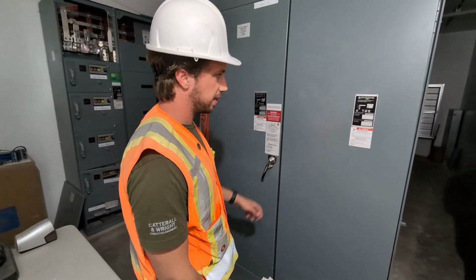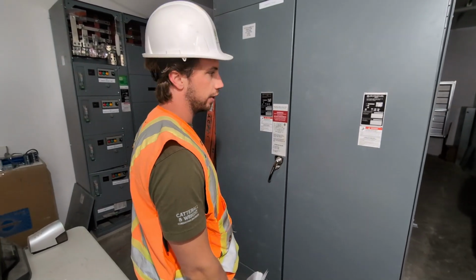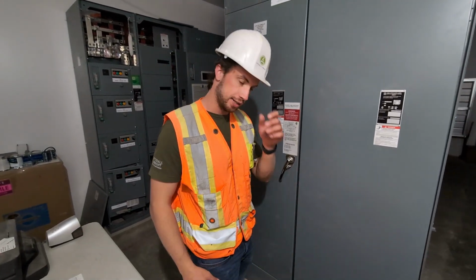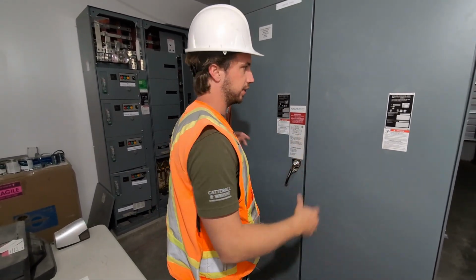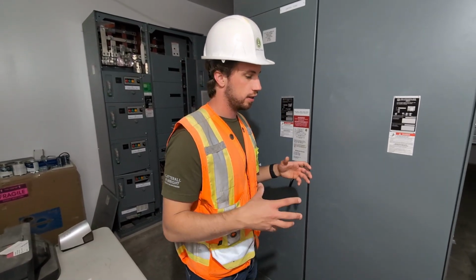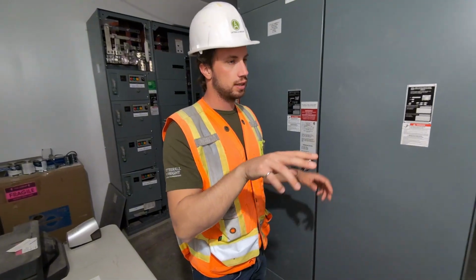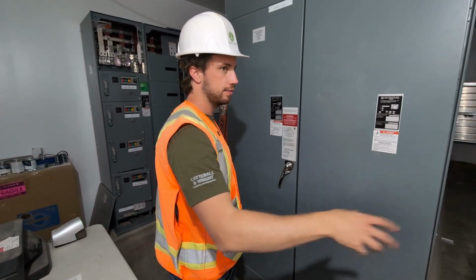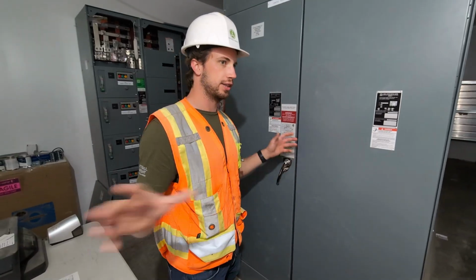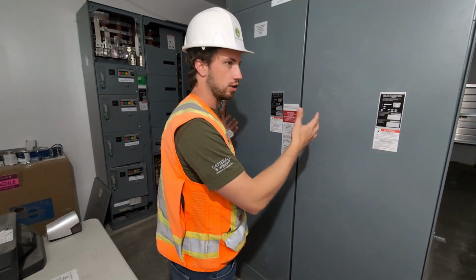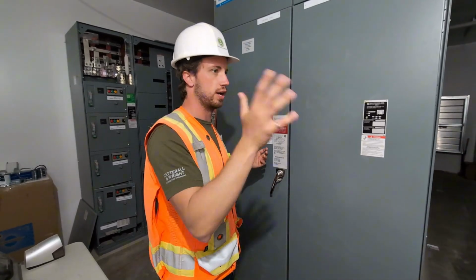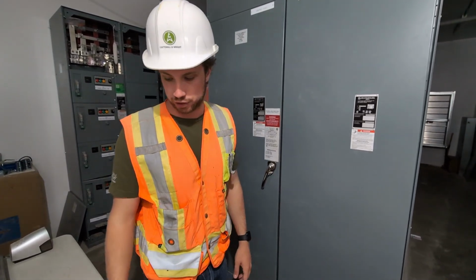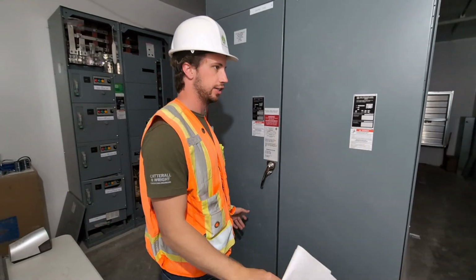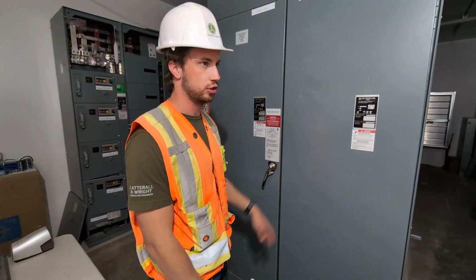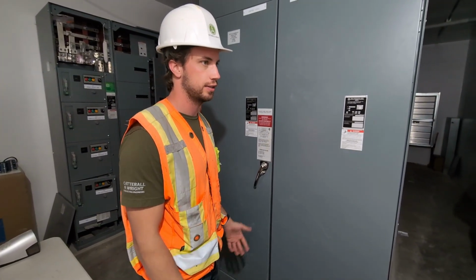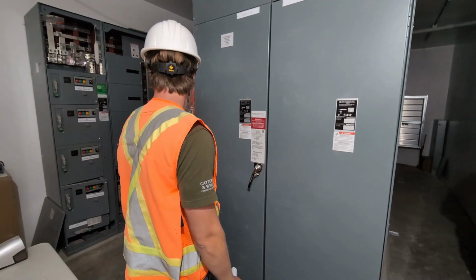Other than just a crazy amount of expensive gear, the only thing I'd comment on is we've split it up a bit, sub-feeding the two different MCC lineups. For example, with two effluent pumps, we've tried to put one on each MCC run, same with recycle pumps and blowers - splitting them up so that if you have to do maintenance on one panel and shut it off, you still have one of each pump. You don't have to shut down recycle, you don't have to shut down blowers.